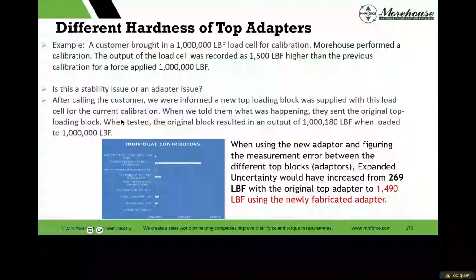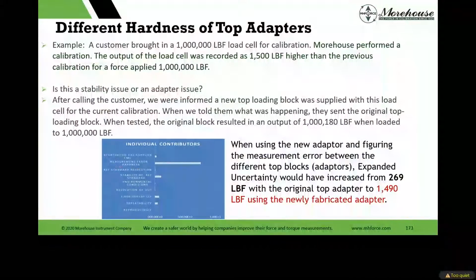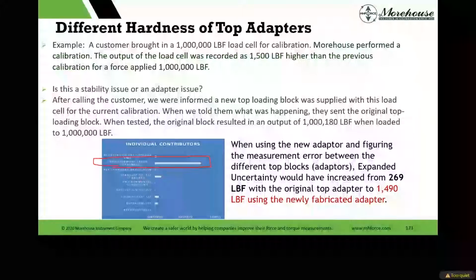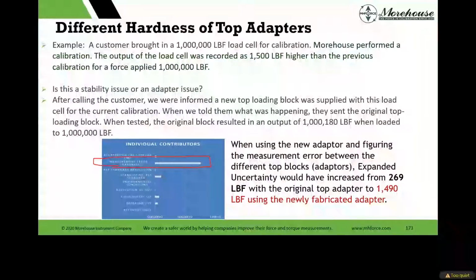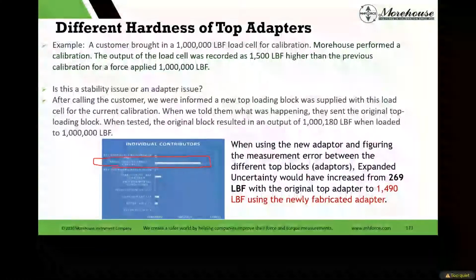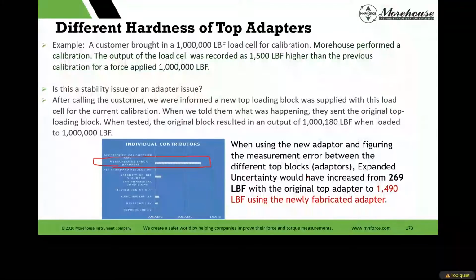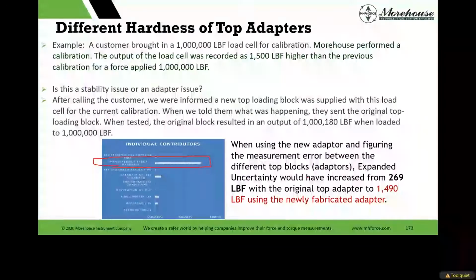So just looking at this, old versus new adapters, no one thought anything of changing adapters into the cal cycle and what it would do. If you look at this number, this individual contributor, it is pretty high, right? Accreditation number, stability of reference standard, all that stuff. What ended up happening is, when we started calculating everything, the expanded uncertainty of 269 pounds would have changed to 1,490 using his new adapter. So basically almost a 6x, just because of the difference in hardness of the adapter.